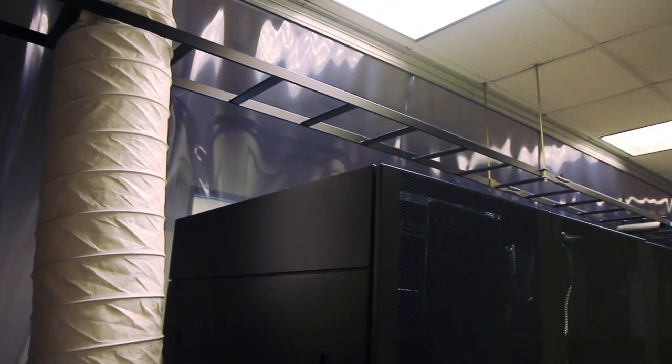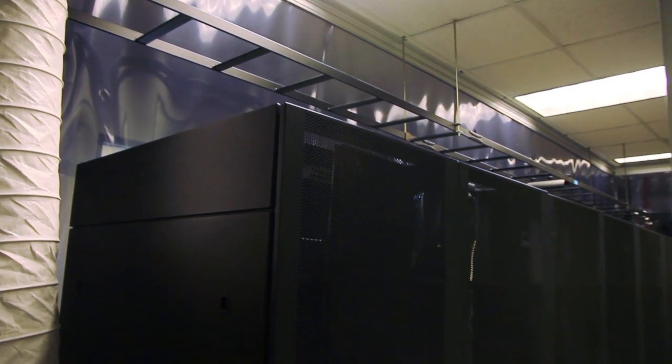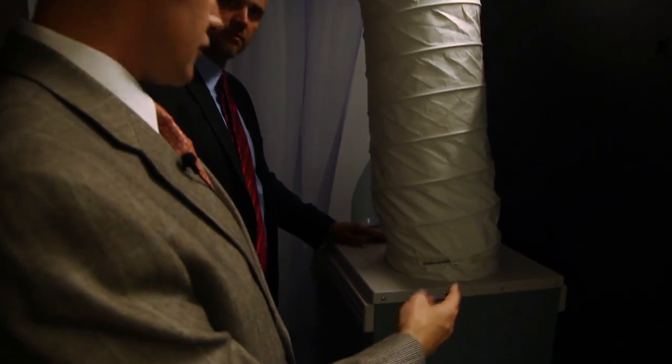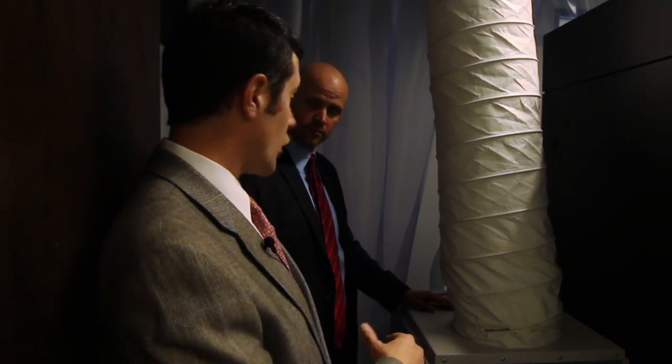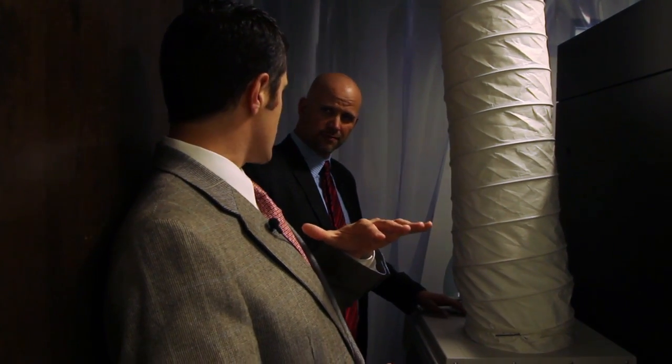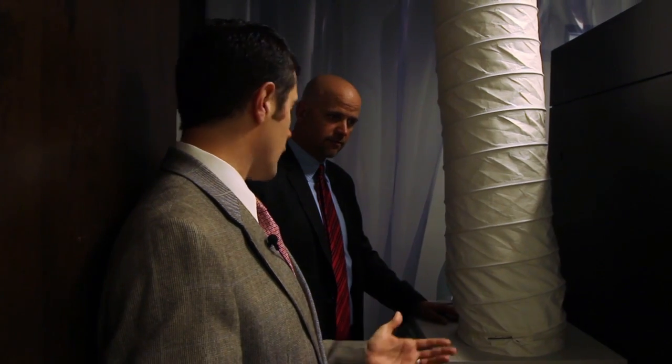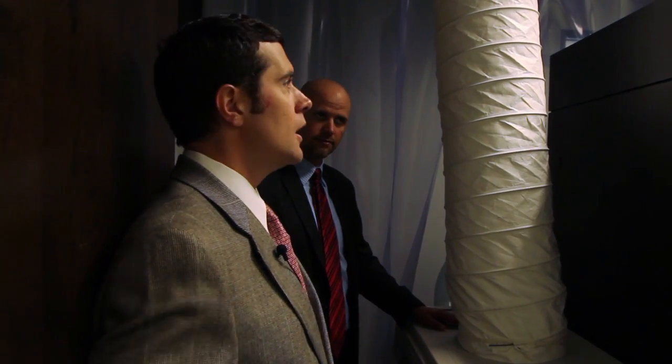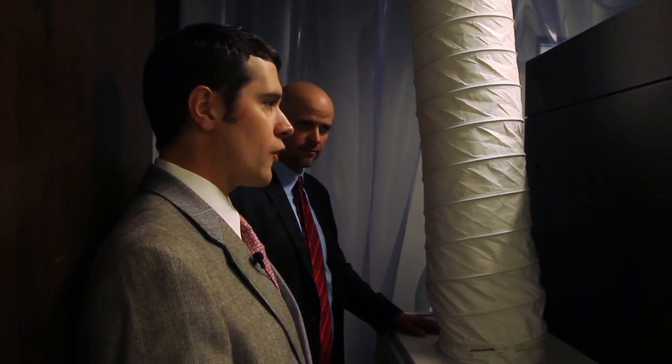Yeah, well, first thing, if we can go back real quick, I'm not sure if you saw at the bottom of the spot cooler, but there are some water sensors down there, because in the case of monitoring, when you're looking for something, you want to be checked for out of band conditions. So in this case, if the spot cooler were to overflow, and the water catcher doesn't work properly or it overflows, then it will tell somebody about it. And that can be said for any number of things.